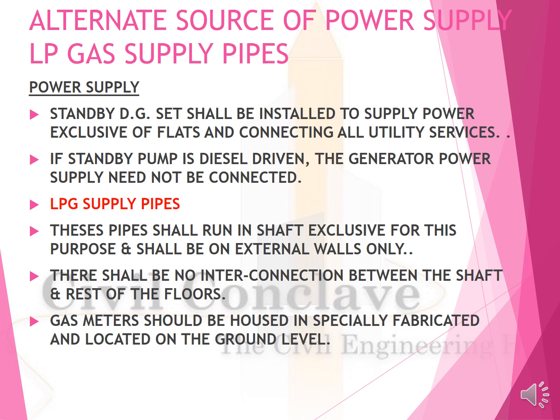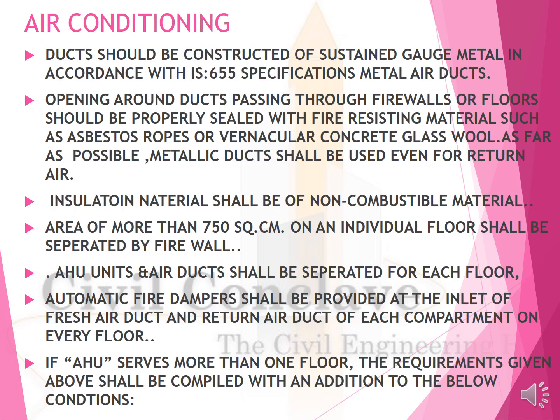LPG pipes. These pipes shall run in a shaft exclusively for the purpose, on external walls only. There shall be no interconnection between the shaft and the rest of the floors. Gas meter should be housed in a specially fabricated enclosure located at ground level. Air conditioning. Ducts should be constructed of sustained gauge metal in accordance with IS 655. Openings around ducts passing through the firewalls should be properly sealed with a fire resisting material such as asbestos ropes, etc. Insulation material shall be of non-combustible material.